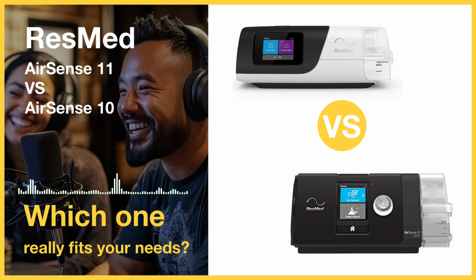And cleaning systems. Any warnings there? Yes, a big one. ResMed explicitly warns against using ozone-based CPAP cleaners, like SoClean and similar devices, with either the AirSense 10 or AirSense 11. They state it can damage the internal components and seals of the machine, and using one will likely void your warranty. Okay, stick to soap and water for cleaning then. That's the manufacturer's recommendation, yes. Regular cleaning with mild soap and water for the mask, tube, and tub.